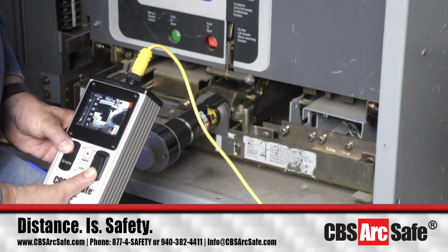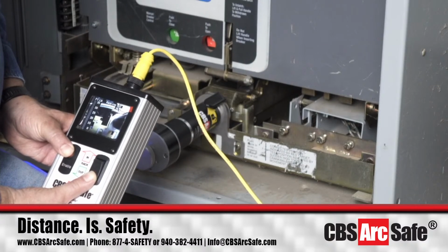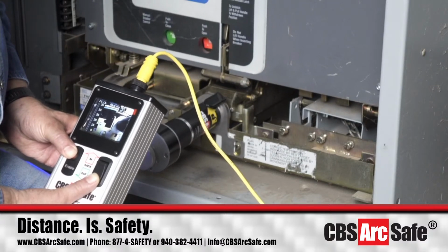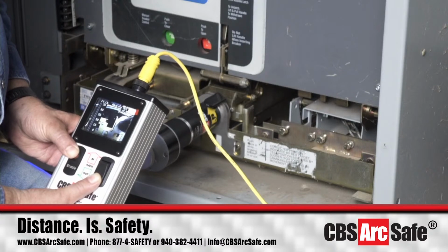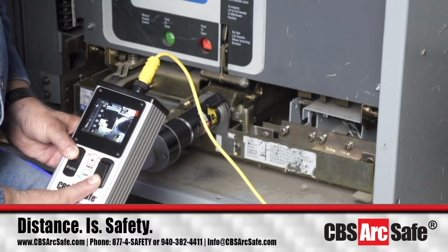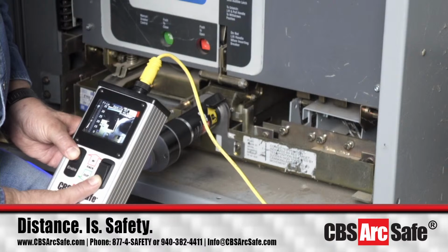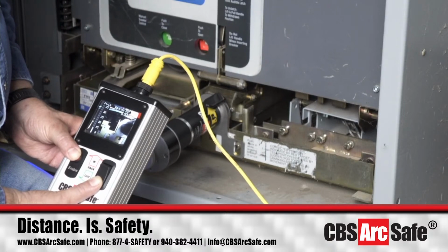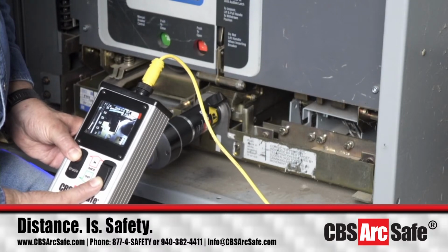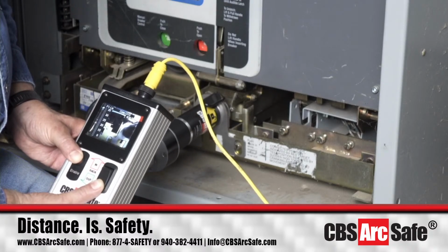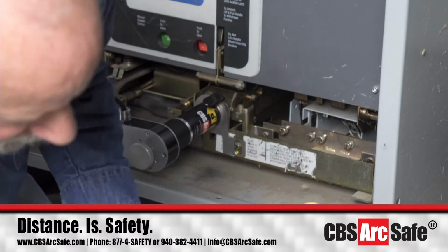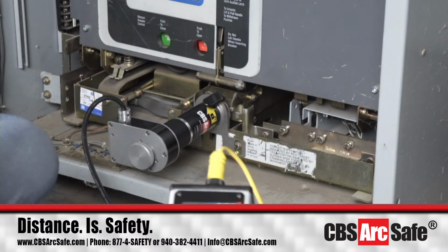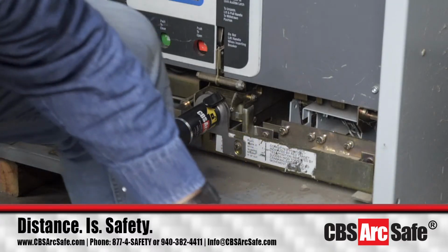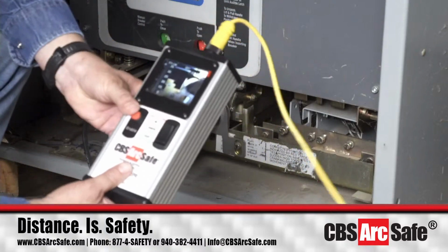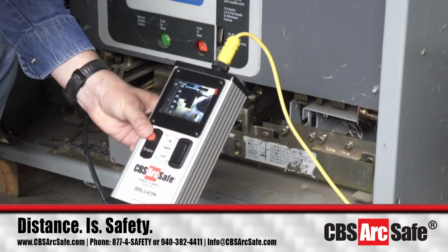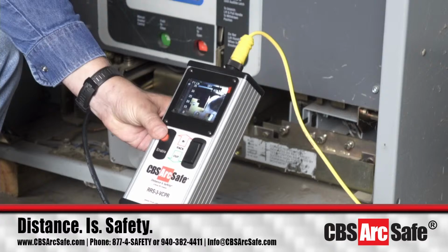When it gets to the end, it will relieve the stress in the mechanism here in just a second after it stops. So I'm just going to keep holding it. And you'll see it stop and then reverse about half a turn. Okay? So that's how we stop and reverse the torque right there. Now, one of the things to note here, as I work to set this back up for the next part, is we're going to go rack it back in now.